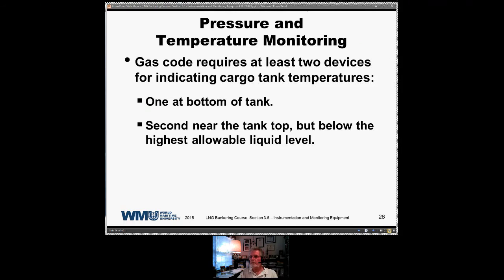flow rates, etc. The gas code requires at least two devices for indicating cargo tank temperature, at least two in each tank. You're going to find that most tanks have more than two. You might just have one at the bottom and one near the tank top, but below the highest allowable liquid level. The highest allowable liquid level is going to be a level indicator, either the high level alarm or the independent high level alarm that actually shuts a tank down when liquid reaches that point. So that temperature indicator has to be below that high level indicator for a tank.